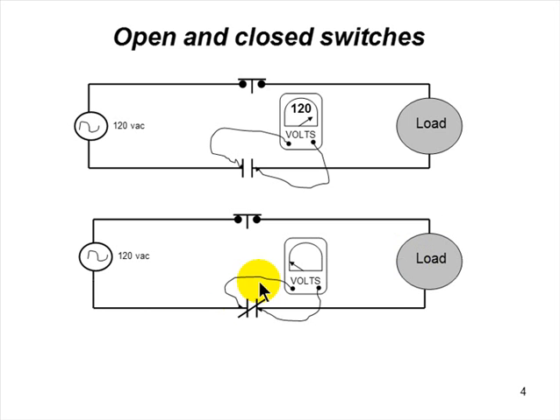How about this case? Same situation, but now the switch is closed. What am I going to read? I'm going to read nothing. If this is a good set of clean contacts, I should have no voltage drop from this point to that point. Because when you read voltage, you're reading a potential. You're reading one of 2 things. This is potential. All right? Let me explain that to you.